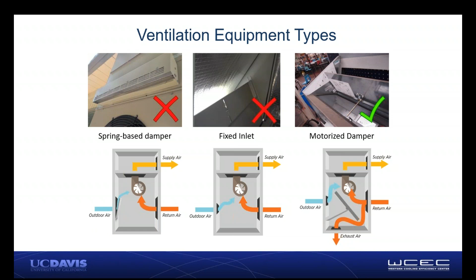In order to improve efficiency, there are some other technology options. Once you have a moving damper, you can think about how you want to control that damper to best increase efficiency. Really common, especially in California and in milder, coastal areas, is to use an economizer. An economizer measures the temperature of the outdoor air, and uses outdoor air for cooling when the outdoor temperature is low. Because the cooling loads in classrooms are really high just because of that high occupant density, it's often colder outside than it is in the classroom, and so you can use the outdoor air for cooling.